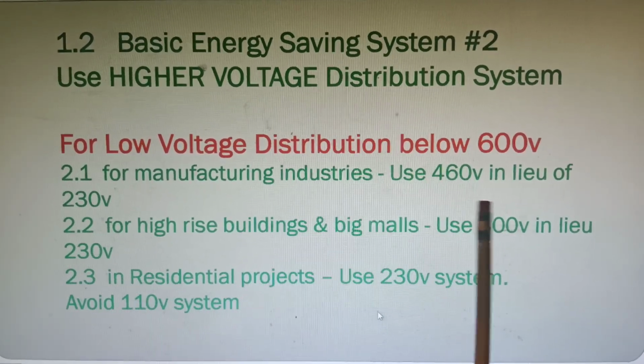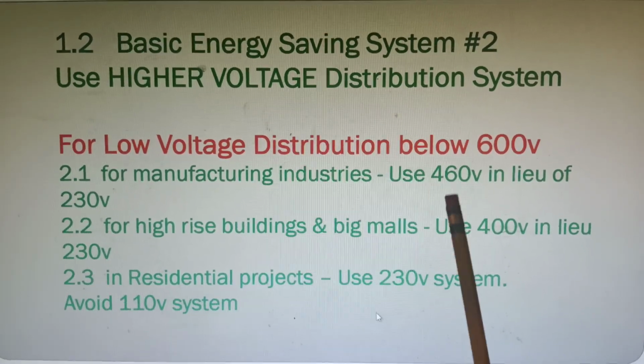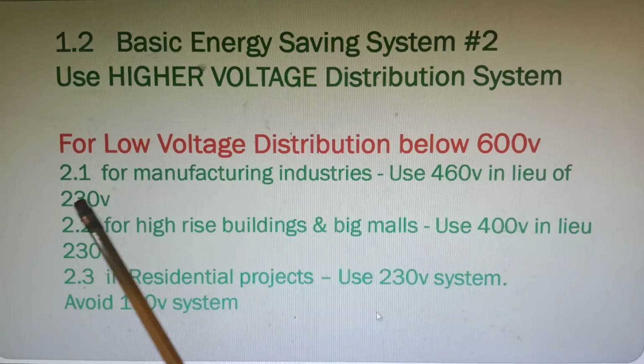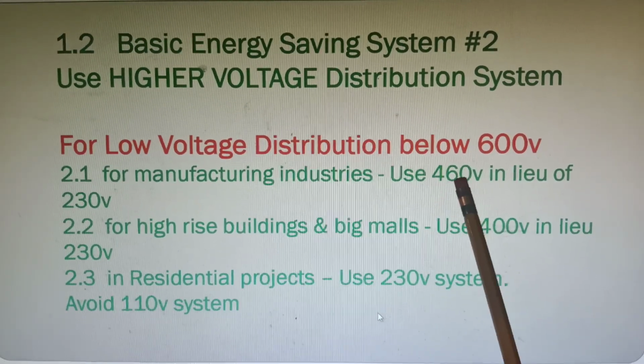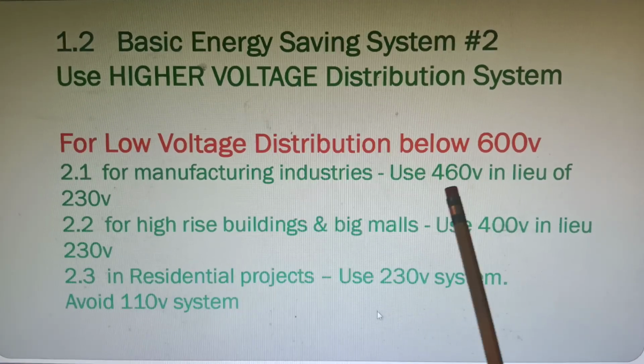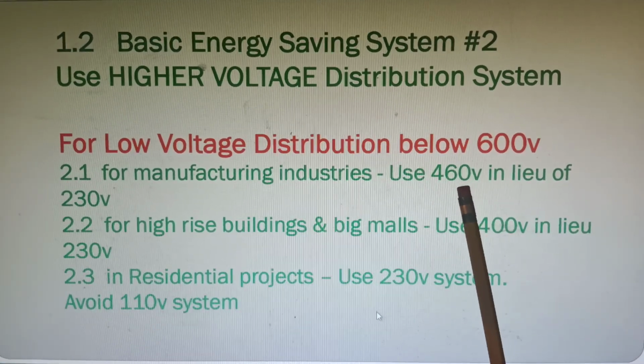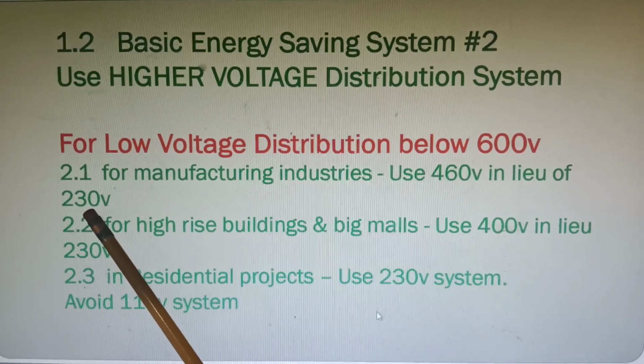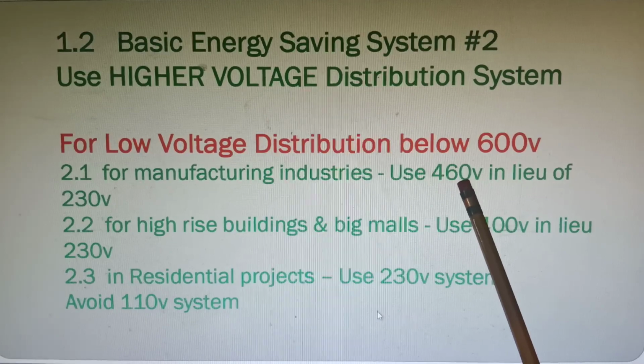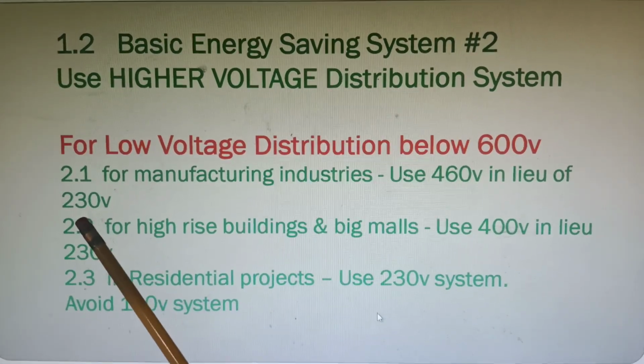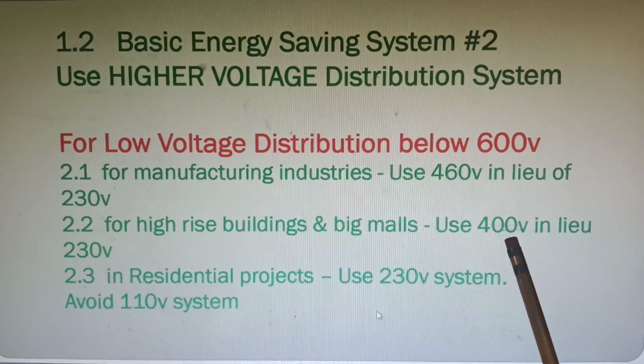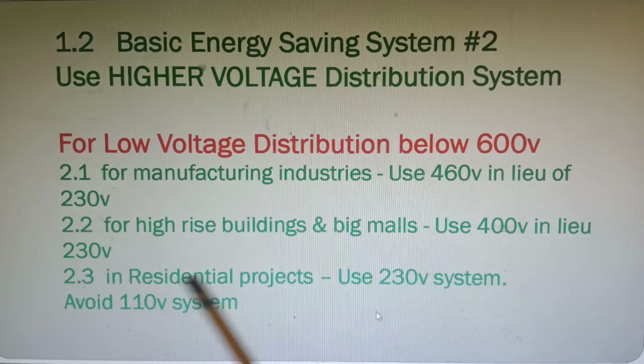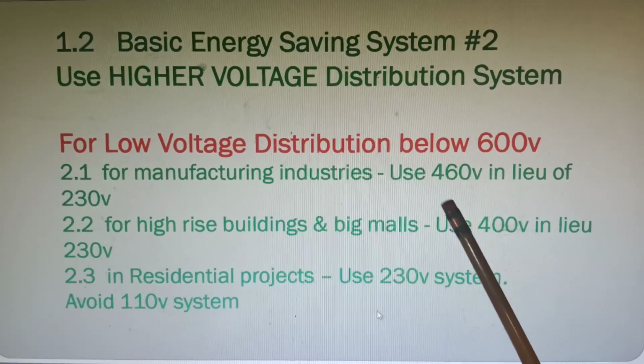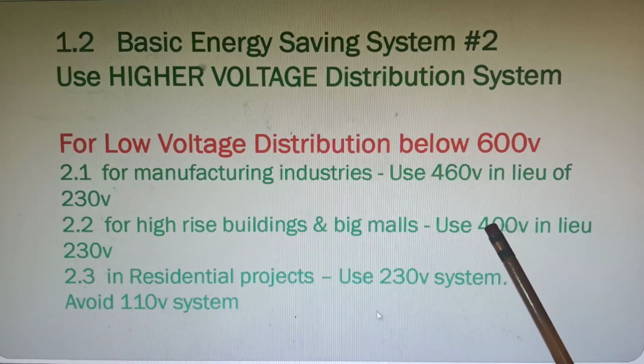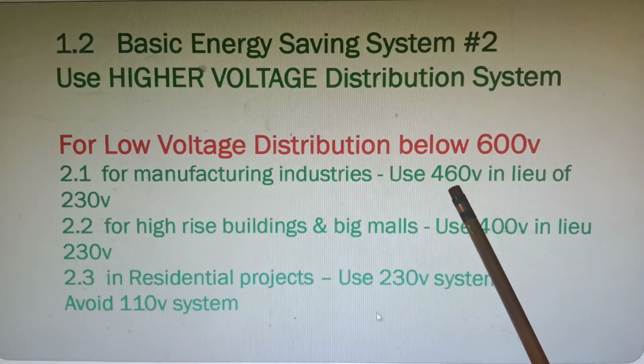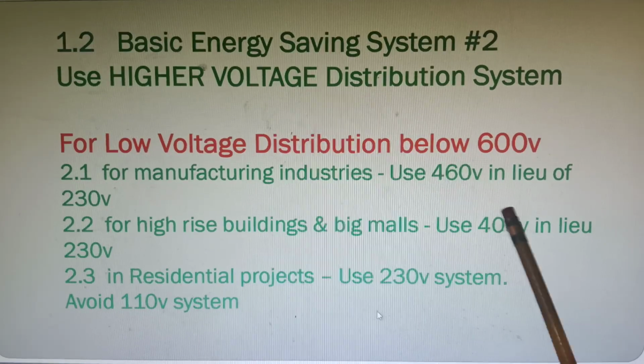Okay, for those who are not electrical engineers, the reason is when you have a higher voltage, as compared 460 versus 230, the current values in the higher voltages are very much lesser than those in the 230 volts. The current is valued at only 1/2 of the currents in the 230 volt system. In the 400 volt system, similarly, they are much lower than in the 230 volts. Of course, you may ask, how about between 460 and 400? Well, of course, in the 460, it's still higher. The current here are much lower than in a 400.